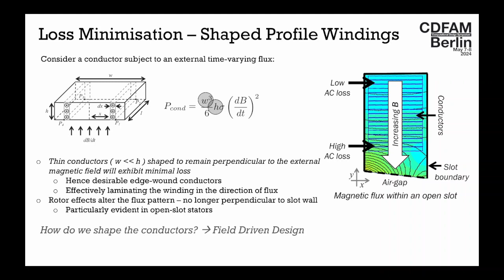In this instance, we've taken a two-dimensional time harmonic finite element model. We've assumed from the beginning that all the conductors are evenly disposed. We then calculated the magnetic vector potential, shown as curved lines representing magnetic flux. We sampled the field at certain points at the top and bottom of each conductor, extracted an equipotential, and joined the equipotentials at the top and bottom together to form a closed surface, giving us a conductor.